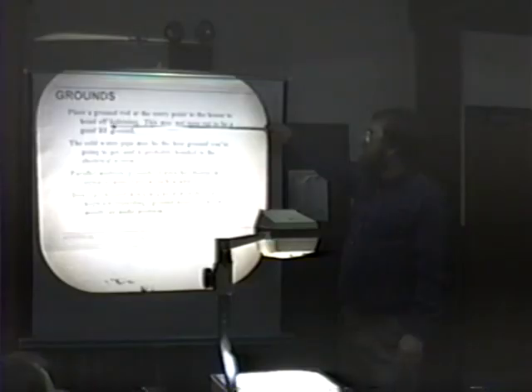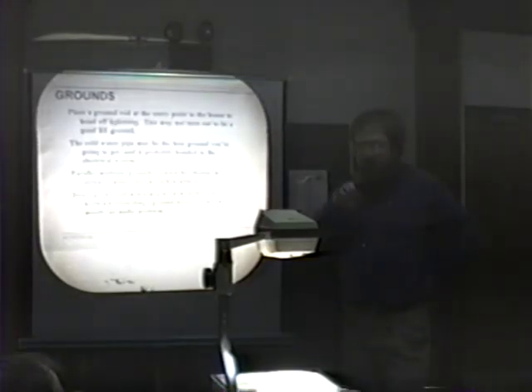Years ago, they did a lot of studies about lightning safety and concluded that you really want an 8-foot ground rod to ensure a good ground connection in dry climates. So let your conscience be your guide. A couple feet of copper tubing pounded in the ground is a lot better than nothing.